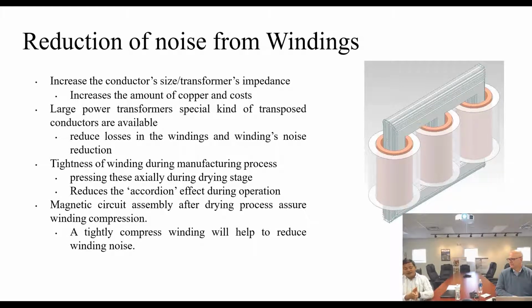Now, after selecting the material, let's talk about the winding construction. Clamping of the winding, just like the core, the winding tightness is also critical, and we ensure that we have proper winding tightness during the manufacturing process. So we do multiple drying processes, and we do the axial clamping mainly during that. By drying, we reduce the moisture from the winding insulation. That will help us reduce all the air gaps in the winding, and we can have as much compression on the windings. Those are at the pre-stage of the winding, and once you make the whole magnetic circuit where the core and the winding are all together, the final clamping of the winding happens, which ensures a uniform specified pressure on the winding. That will help us reduce the transformer noise, and mainly the noise generated by the winding.